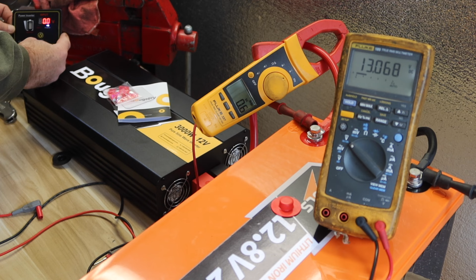This claims it's sitting at 12.8 volts. I believe the fluke meter is over the little remote power panel. The panel itself is reading almost a full battery at 12.8 volts. And that part of the panel shows 122 volts AC, 12.9 volts input, producing 60 hertz. Now we're going to hook up a 1000 watt heater to that inverter and see what occurs.